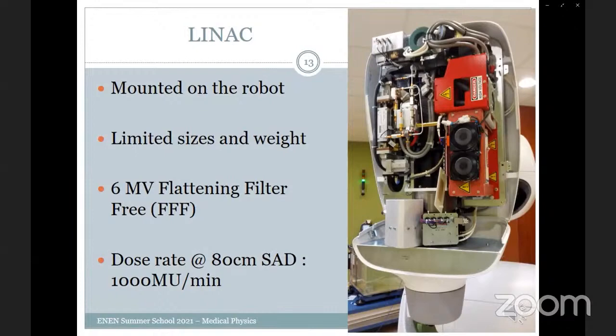So all this LINAC head is mounted on the robot, and it can deliver 6 megavoltage flattening filter free beams. The dose rate at 80 cm source axis distance is 1000 monitor units per minute, because you have to be as fast as possible, because the robot has to go through a lot of beams, a lot of directions, so treatments can last long on a CyberKnife machine. So you have to use as high monitor units per minute, as high dose rate as possible.